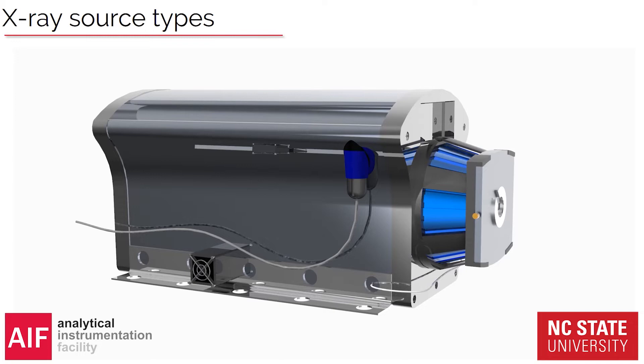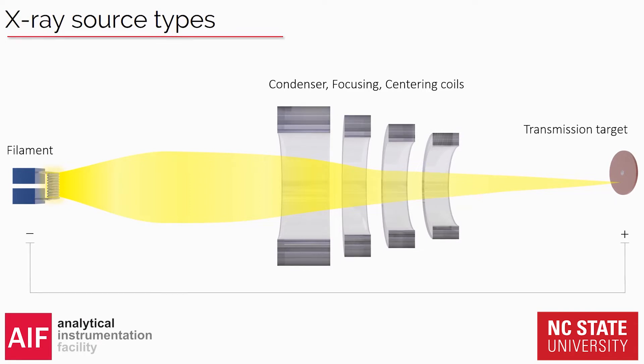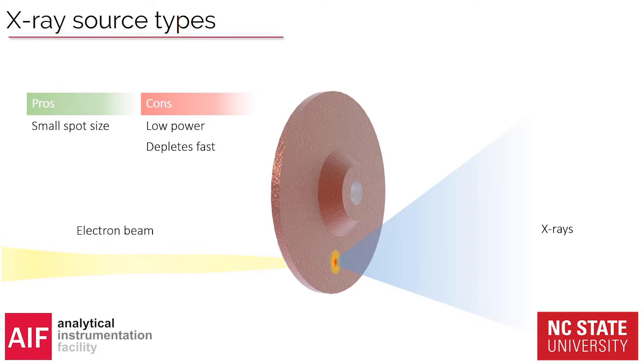There are many different types of X-ray sources. The transmission target setup has a filament where you shoot and focus the electrons and hit them into a thin disc — the transmission target — where the electrons hit and you get X-rays. This can be quite nice because you can get pretty small spot sizes if you have a very thin target. However, if you have a very thin target you will get a lot of heat buildup and it will deplete very fast, so you can only use low power and have to change it out a lot.